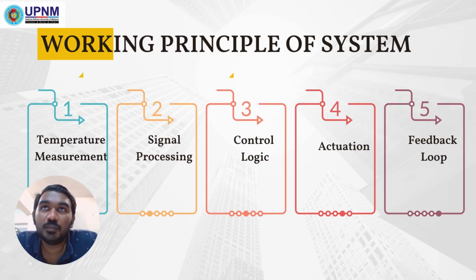Hello, now we are going to talk about the working principle of the thermocouple type K sensor system. A thermocouple is made up of two dissimilar metal wires which are connected at one end, known as the hot junction. The remaining end, known as the cold junction, is connected to a measuring instrument. Temperature gradient. The temperature inside the boiler, the hot junction, will form a temperature gradient with a known reference temperature, which is called the ambient or cold junction. The Seebeck effect causes an electrical voltage to be created when there is a temperature difference between the hot and cold junction. This produces voltage. The output voltage is directly proportional to the temperature difference.